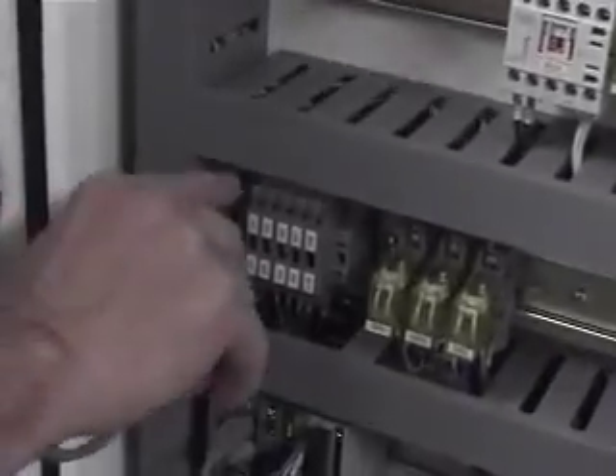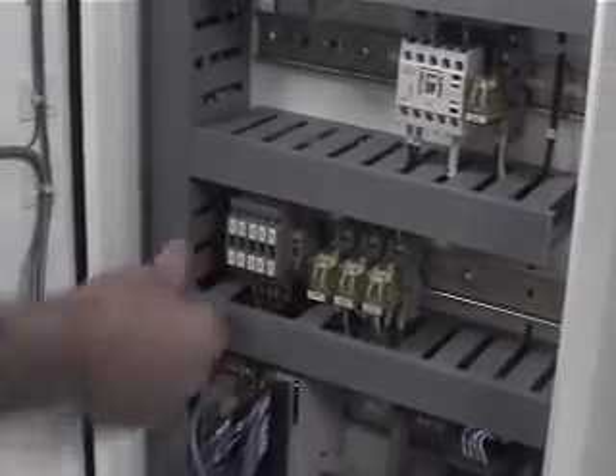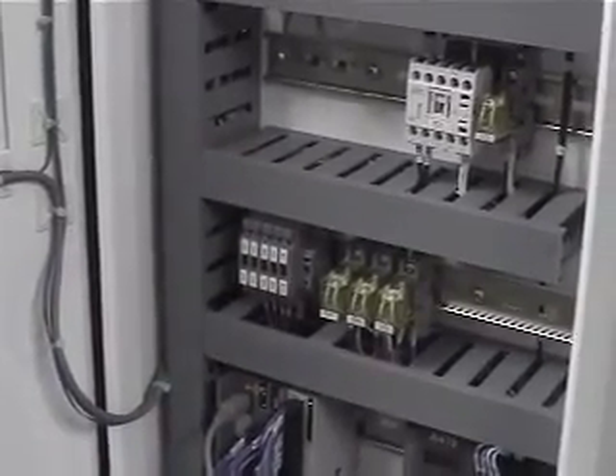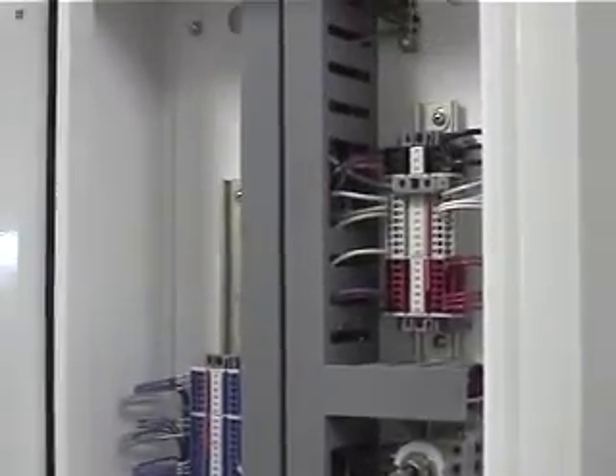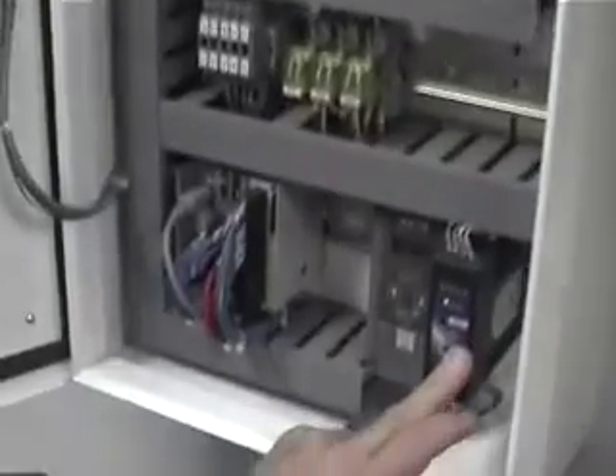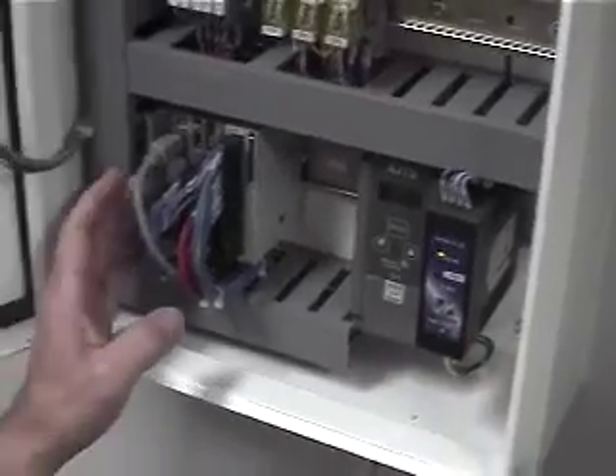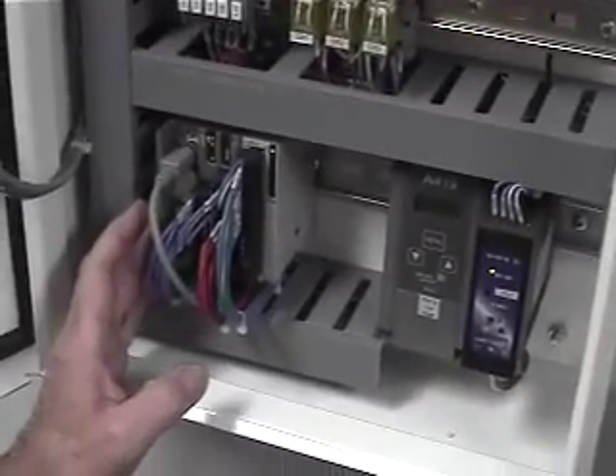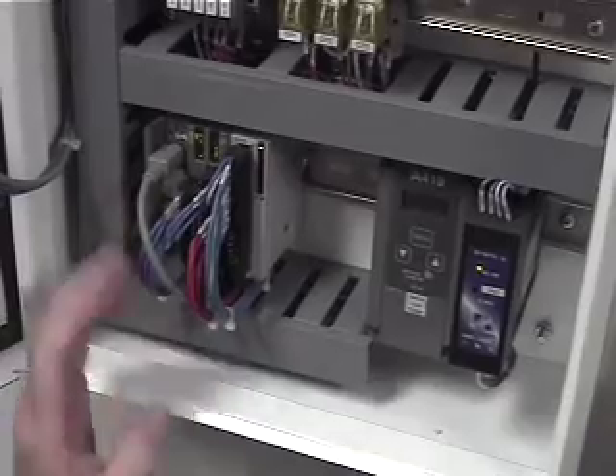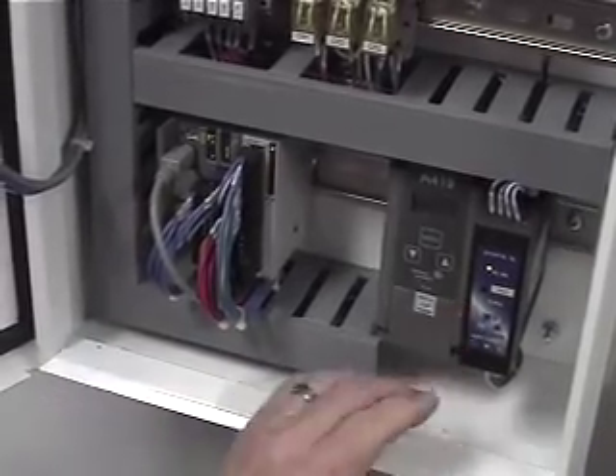We protect the output of the PLC with the COMs and a fuse here. And then 221 is actually for the operator interface. That kills the low voltage, the operator interface. So if something happens to it, we try not to burn things out. So we've got a lot of protection between the breakers and the fuses. Everything is protected really well. Talked about the 24-volt power supply. The PLC and the operator interface are both 24 VDC. And that's where they get their power source, power supply.